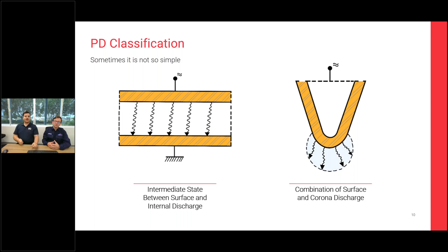Where it gets a little more complicated in outdoor yards is the trickier types of discharge, things like contact types and small spark gaps where they're discharging, because that is very prevalent in outdoor yards. So in this project, we needed a way to distinguish between the discharges in switches, the corona discharge and all the little things which are quite common and not necessarily a problem. We had to disassociate that from the true internal void problems which we thought may have been leading to a failure. And that came with its own challenges.